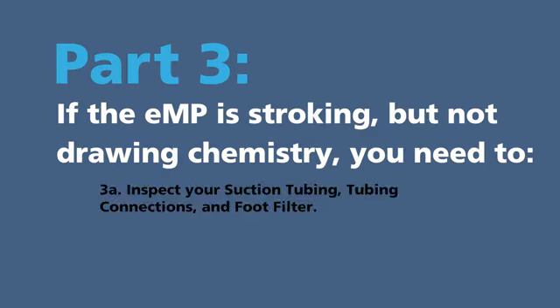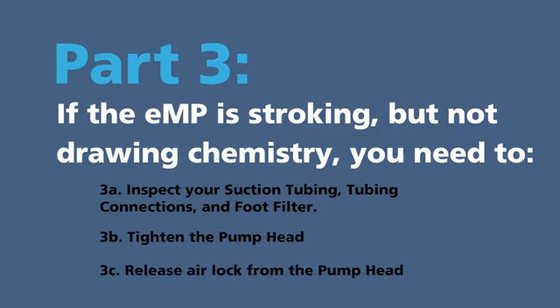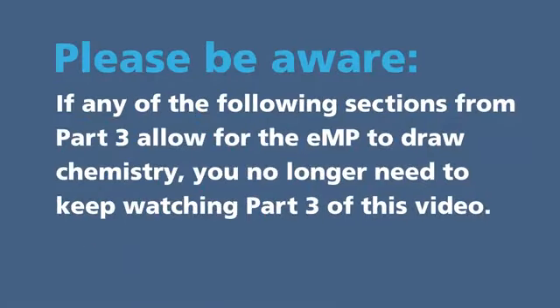Part 3. If the eMP is stroking but not drawing chemistry, you need to 3A. Inspect your suction tubing, tubing connections, and foot filter. 3B. Tighten the pump head. 3C. Release airlock from the pump head. Please be aware, if any of the following sections from Part 3 allow for the eMP to draw chemistry, you no longer need to keep watching Part 3 of this video.